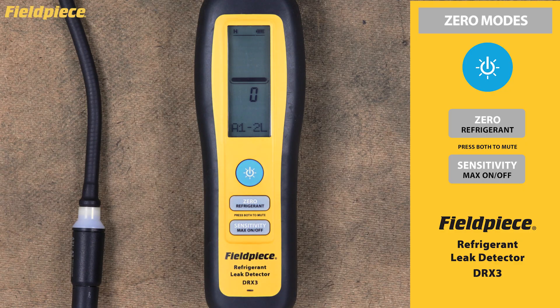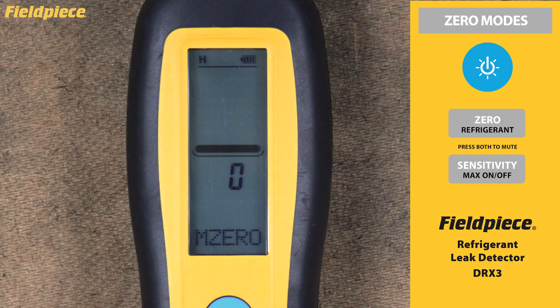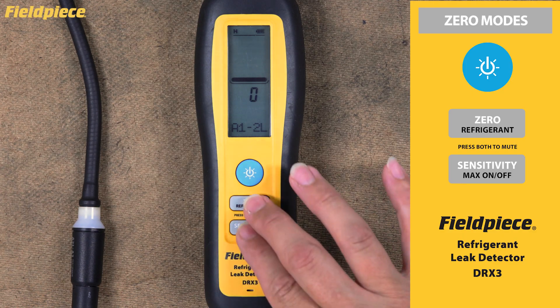Zero Modes. Understanding zero modes is essential for accurate leak detection. The DRX3 offers both automatic and manual zeroing options. The unit starts in automatic zero mode by default, where it sets a new zero point approximately every three seconds. You'll know it's active when the selected refrigerant blinks in the message line, indicating the unit is creating a new reference baseline. To toggle between auto and manual zero mode, press and hold both the zero and sensitivity buttons for more than two seconds. When manual zero mode is active, you'll see MZERO displayed on the screen; when you switch back, you'll see AZERO.